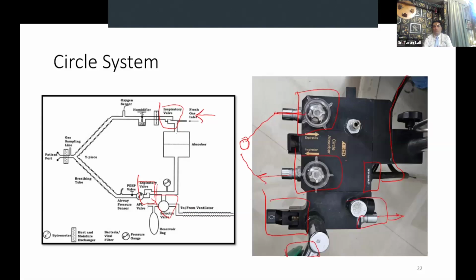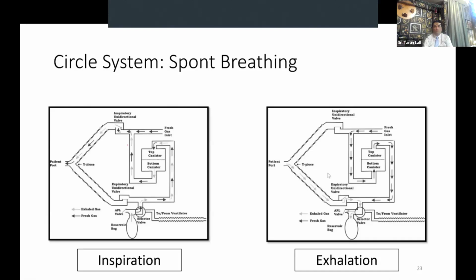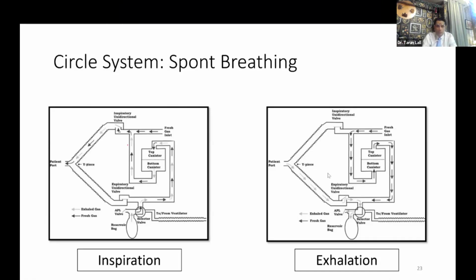So now how do gases flow? Let us see how this system behaves during spontaneous breathing. What you have to remember is that in any circuit, whether it be your circle system, your Bain circuit, or A, B, C, whichever circuit you are using, in spontaneous breathing the APL valve opens during the phase in which the pressure is higher. In spontaneous breathing, you know that it is negative pressure inspiration and the pressure rises slightly during exhalation. Whereas in controlled breathing, whether manual or ventilator breathing, the pressure is higher in the inspiratory phase, positive pressure ventilation. So that is why in manual or controlled breathing with a ventilator, the APL valve will open during inspiration.